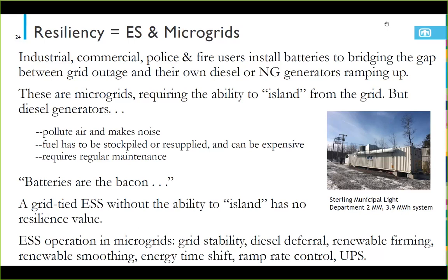places like Intel here in our own Middle Rio Grande Valley, commercial and industrial operations that can't afford to have a power outage, police and fire who don't want their systems to go down, even in the briefest power outage, have batteries that kick in when the outage occurs, because batteries can kick in really fast, in milliseconds or a second or two. The battery can detect the outage, kick in, provide the power until the diesel or natural gas systems ramp up, and then the battery system can go off. Now, in those situations, you need a relatively small battery that stays charged all the time. It's always ready for the power outage. And that's one application. That is a microgrid.